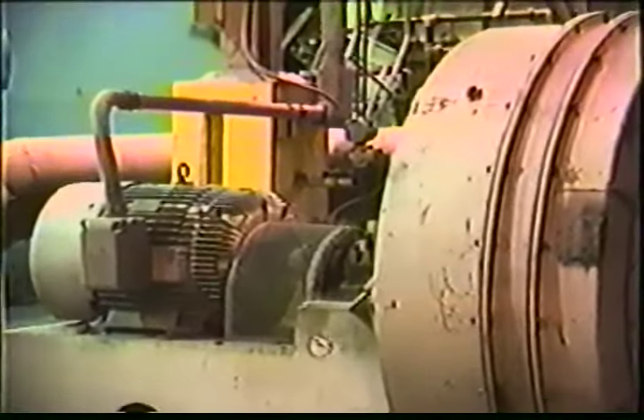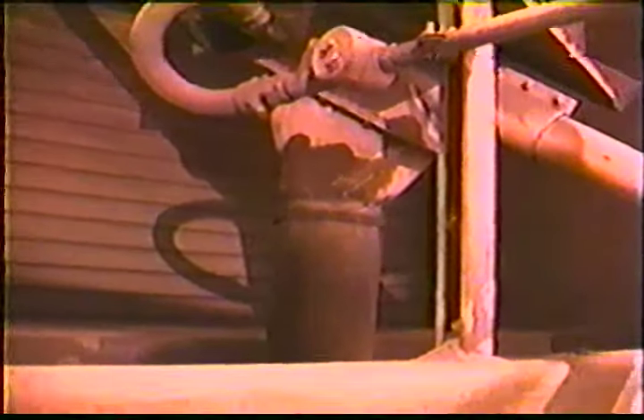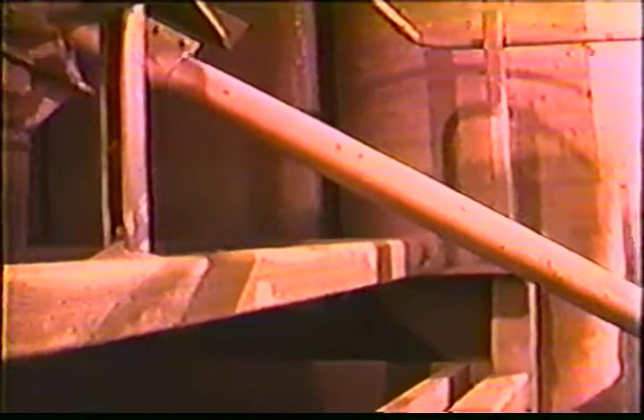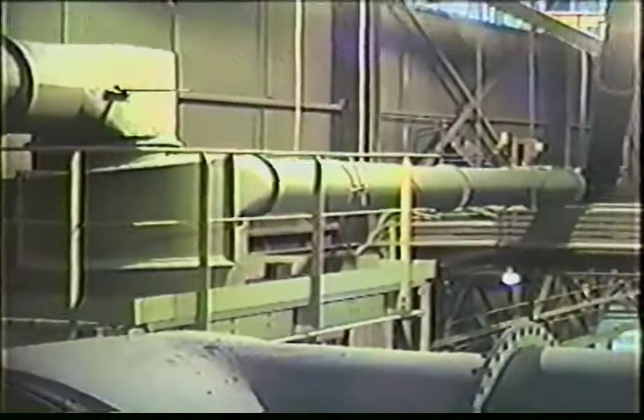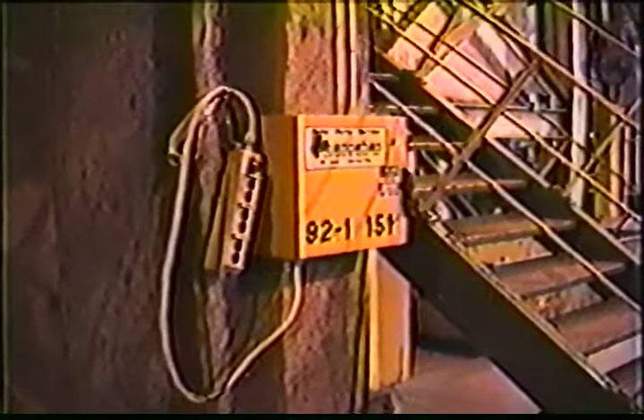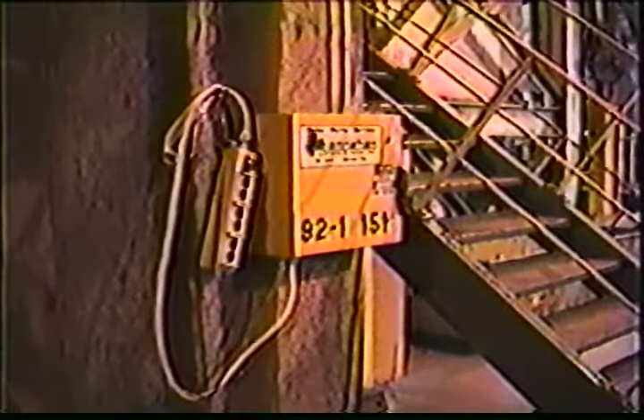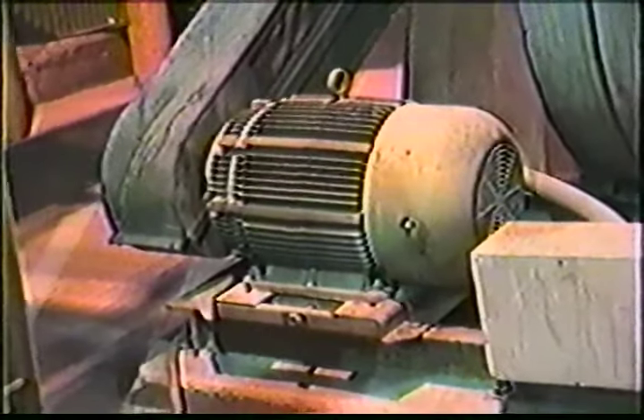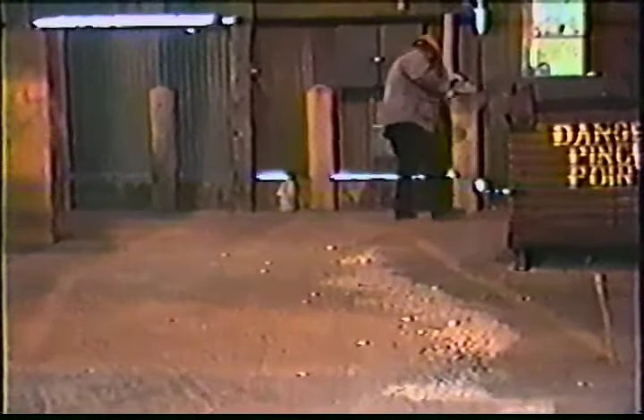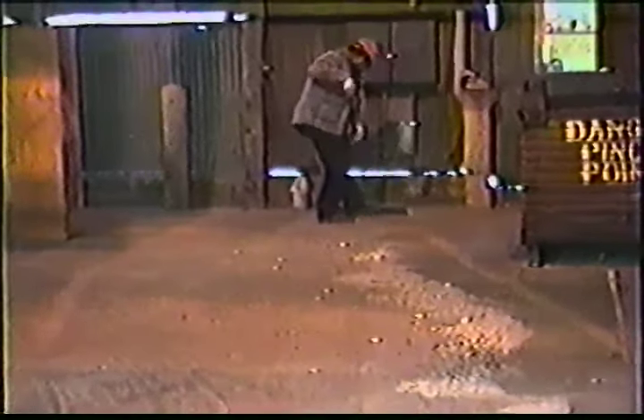You also need to know that we have designed into our equipment systems safety features appropriate for hazardous dust environments. All equipment at the offline and storage silos was designed in accordance with Alcoa Engineering Standard 18.4.2. Ductwork is specially designed to minimize dust accumulations. All electrical equipment was specified for electrical explosion hazards. So, it's clear that employees have a role to play in helping to prevent explosions. Here's what you can do to help prevent an explosion.